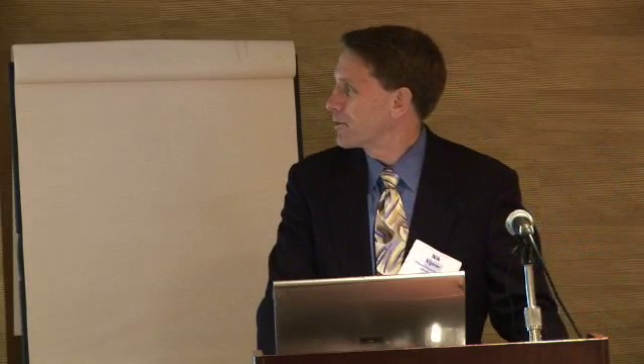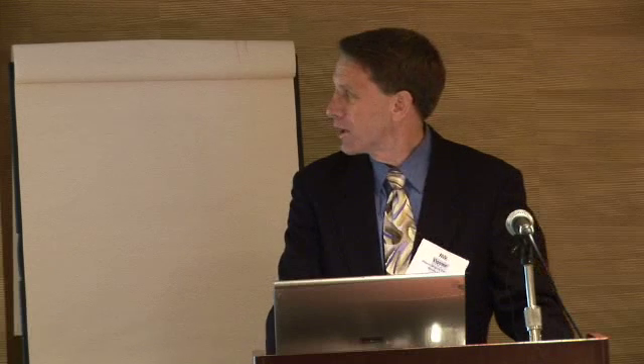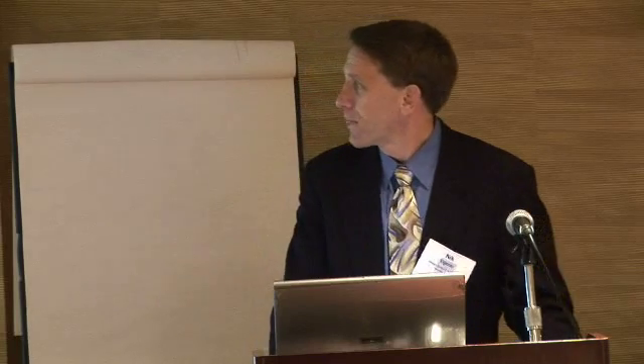Again, what happens when we put insulation on masonry? Again, another analysis you can run with WUFI. You put a 2-inch semi-permeable insulation on a brick masonry wall and a 6 mil poly vapor retarder. People still do that. So some of my practice is based on the fact that people still do this. You put a monitor point there. And then you start looking at the relative humidity on the interior side of the insulation.